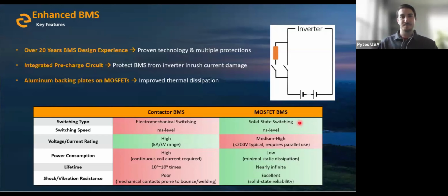One of the things that the MOSFET can also do a bit better is a much faster response time compared to the contactor, with virtually no or very low power consumption, because you're not needing any power from the batteries to maintain that MOSFET in one state or the other like you would have with the contactor. As I said, super long lifespan, nearly infinite compared to the life of a contactor BMS, and just excellent quality and reliability. Again, no moving parts means fewer things that can fail and wear out over time.